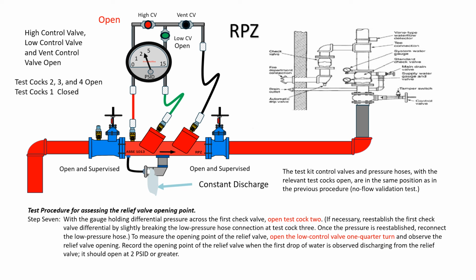Test procedure for assessing the relief valve opening point. RPZ. The test kit control valves and pressure hoses, with the relevant test cocks open, are in the same position as in the previous procedure, no flow validation test. Step 7. With the gauge holding differential pressure across the first check valve, open test cock 2. If necessary, re-establish the first check valve differential by slightly breaking the low pressure hose connection at test cock 3. Once the pressure is re-established, reconnect the low pressure hose. To measure the opening point of the relief valve, open the low control valve 1/4 turn, and observe the relief valve opening. Record the opening point of the relief valve when the first drop of water is observed, discharging from the relief valve. It should open at 2 psid or greater.